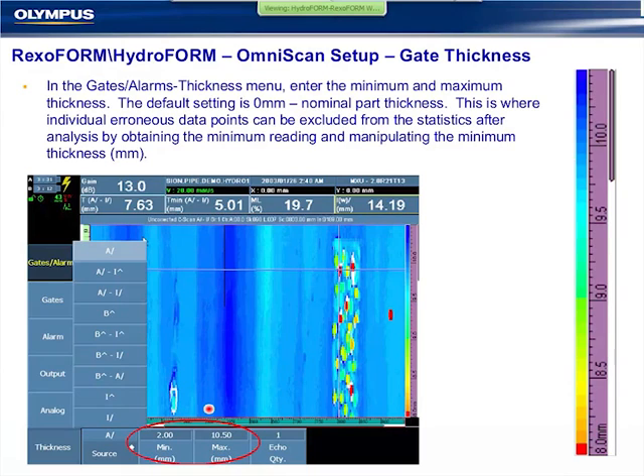So once I've acquired the data between 0 to the nominal thickness, I will determine my lowest point in the C-scan and make an adjustment here, so those invalid or non-relevant readings, no acquisition readings, 0, one of the gates bled into the other gate, I can eliminate those erroneous readings from my data by limiting it here. And again, that sets the purple scale that you see here beside the C-scan.